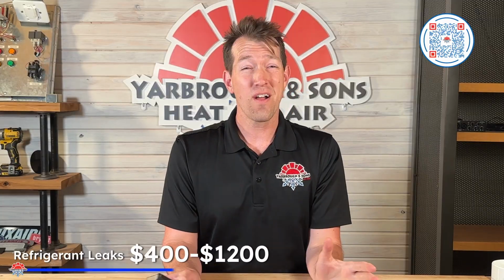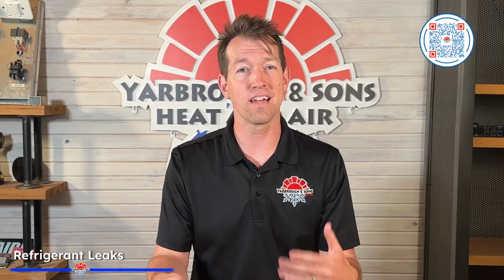Moving on from contactors, refrigerant leaks. These are real fun. $400 to $1,200-ish. When a tech tells you your system's running low on refrigerant, there is one thing you need to understand immediately, not later, immediately. Refrigerant doesn't just disappear. Your system is a closed loop. If refrigerant's low, there's a leak. A technician who charges you to recharge the system without finding and fixing the leak has done you no favors. The refrigerant will leak out again, usually within the same season, and you'll pay for another recharge. The correct repair is find the leak, fix the leak, pressure test the system, and then recharge it.